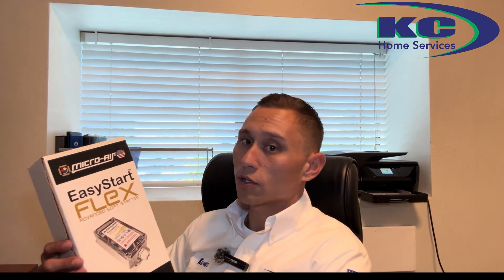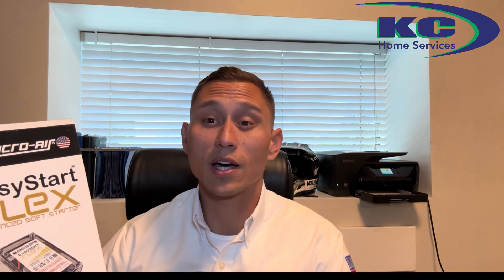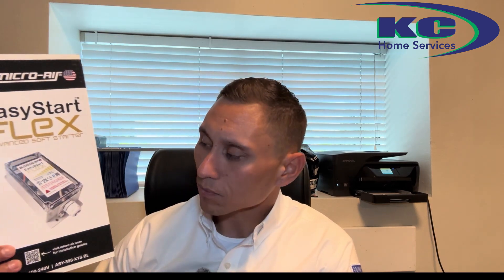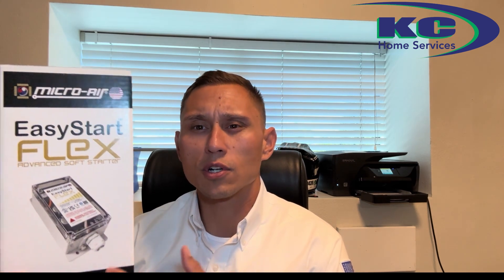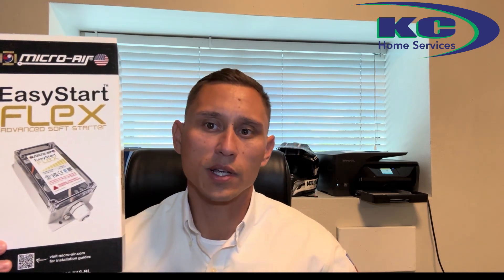One of the biggest things we can do to combat this is by putting a soft start kit on. One of the best performing soft start kits we've found is easily the Easy Start Flex Advanced Soft Starter. This kit is not something traditionally stocked at supply houses or anywhere in town that's easy to find. It was typically a product you could only find online, and it became increasingly popular amongst serious service techs across the United States. You were starting to see videos pop up on TikTok, Instagram, and YouTube talking about this product.